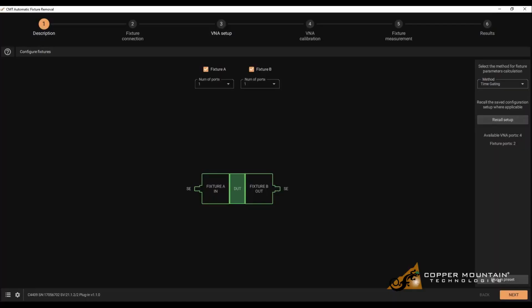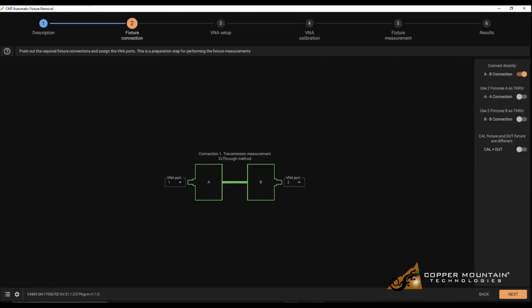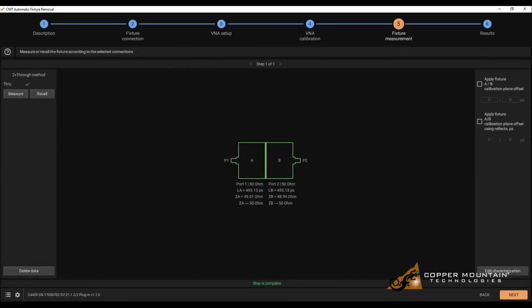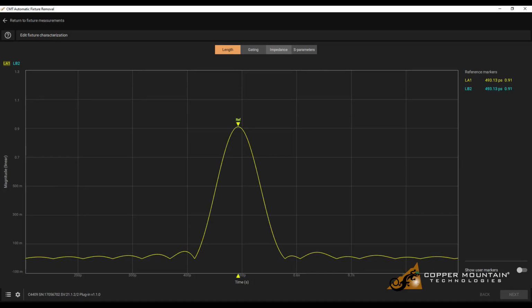In this video, I'll be demonstrating automatic fixture removal using Copper Mountain Technologies Vector Network Analyzers. AFR is an intuitive software plugin.